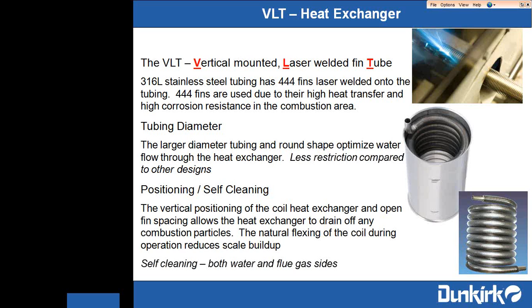And so as the boiler heats up and cools down through those cycles, you get a lot of expansion and contraction within that heat exchanger. We downfire within that combustion chamber, so the condensate that's created as part of the combustion process will self-clean and continually wash the heat exchanger surface, preventing sediment buildup completely. So unlike a lot of the competitors out there, the contractor doesn't have to go in and clean the heat exchanger annually to maintain the warranty. The design of the boiler makes it completely self-cleaning.